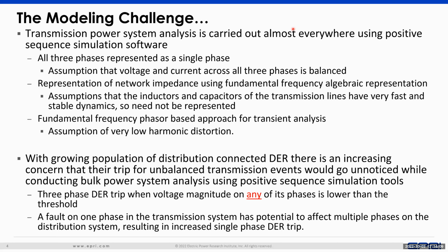Now, this becomes a challenge with DER because DER can trip on single phase voltage. Even a three-phase DER, with three phases of voltage, can still trip if there is only a single phase event or single phase voltage that occurs.